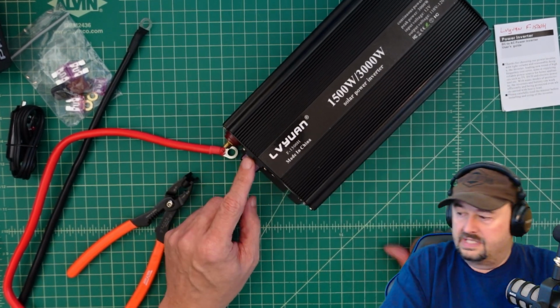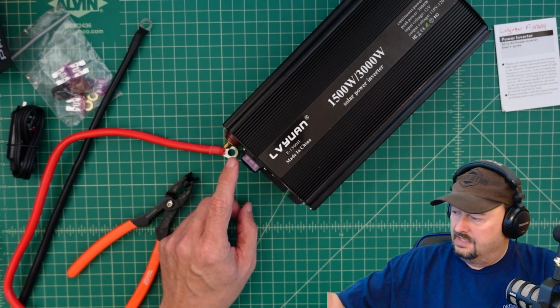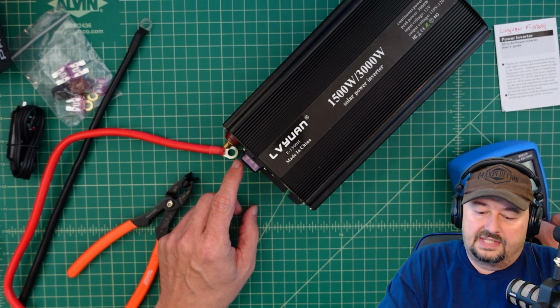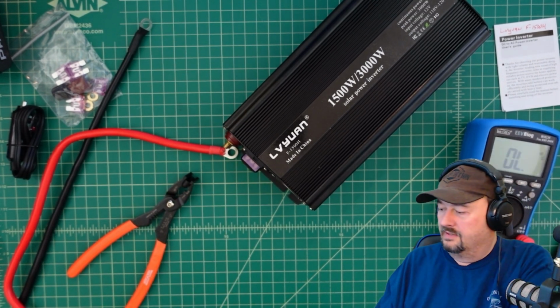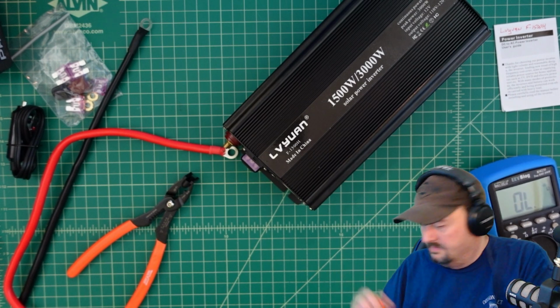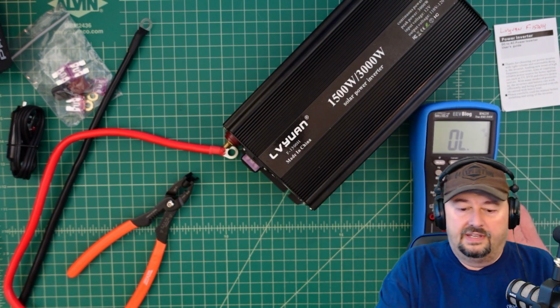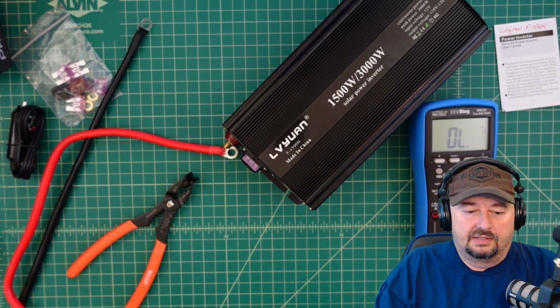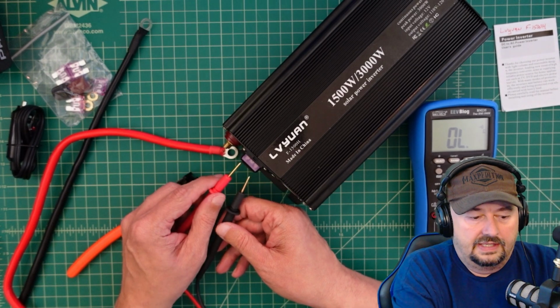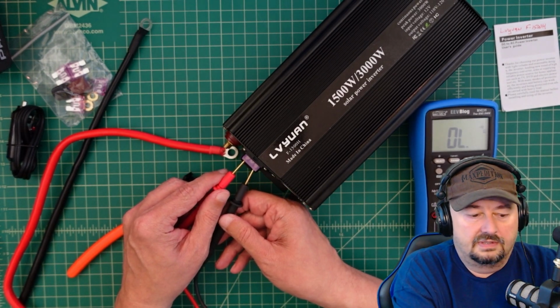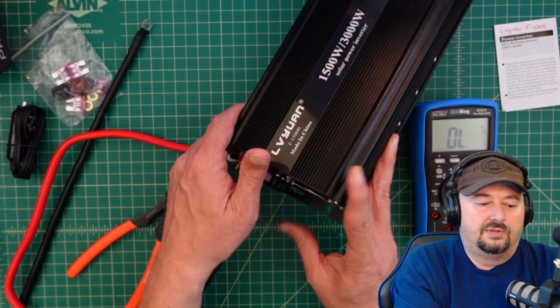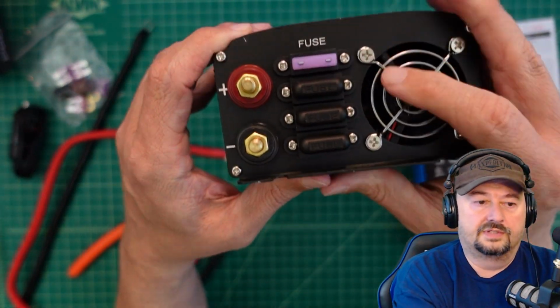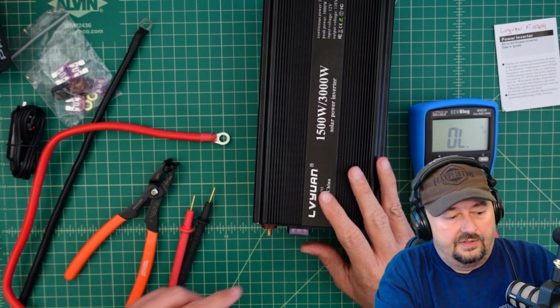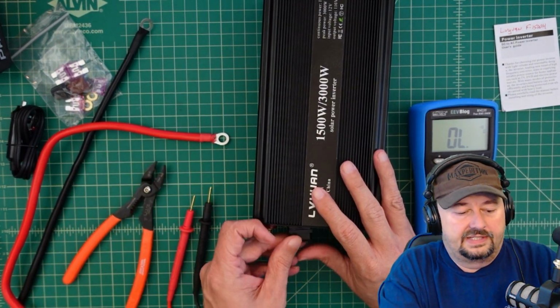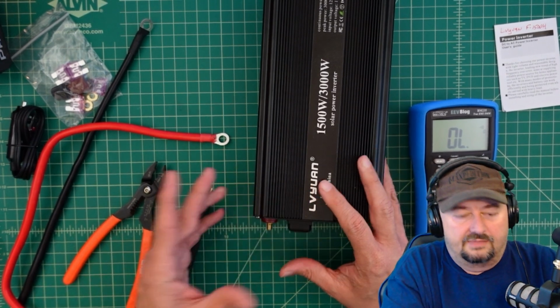One of the things I was going to show you is that you can quickly test these fuses to see if they're blown or if you have a problem. What I have here is a multimeter set on continuity testing, and I just touch the exposed parts of the fuse to see if we have continuity, and we do, the fuse is good. That's these two metal parts right here that I touched. I already went through and checked all of the fuses on this device, and they're all good. That's just something I typically do before I go monkeying around or messing with stuff.